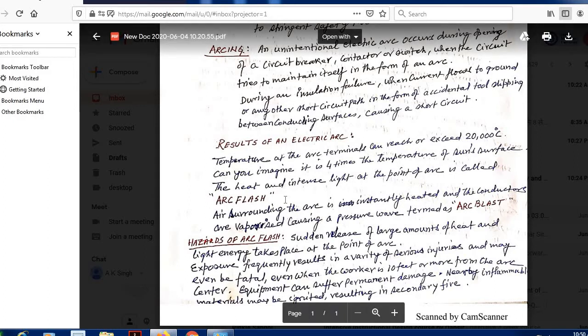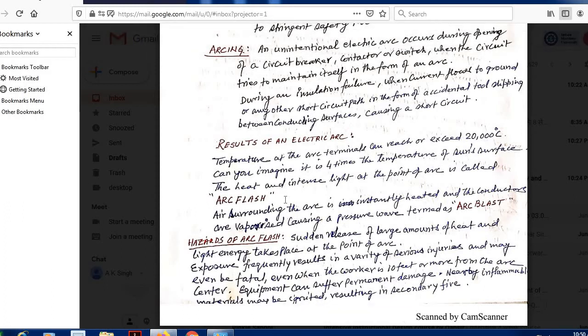Similarly here also, when we are interrupting any circuit, when the two contacts are coming apart, the arc is established. And do you know what is the temperature of the arc at the point of separation? At the point of arc, the temperature is 20,000 degrees centigrade. Now just imagine, you are using copper conductors, and at 20,000 degrees centigrade, what will happen to the copper conductor? It will melt and vaporize, if the temperature continues for a longer period. So the biggest problem is how to extinguish this arc within the shortest period, so that it doesn't damage the equipment and the system. This is one big problem associated with this high voltage system.